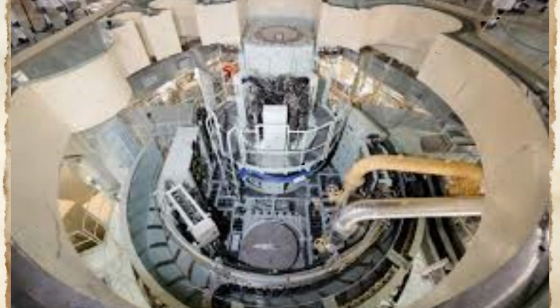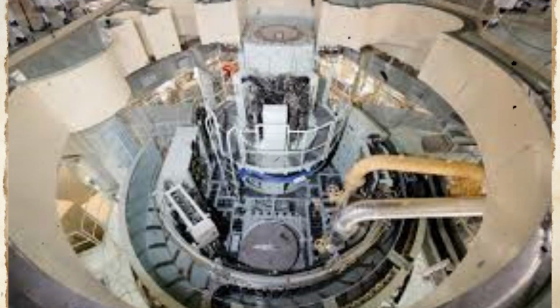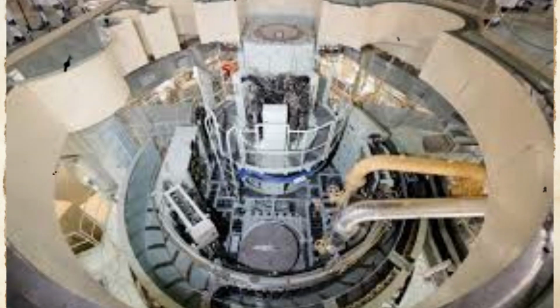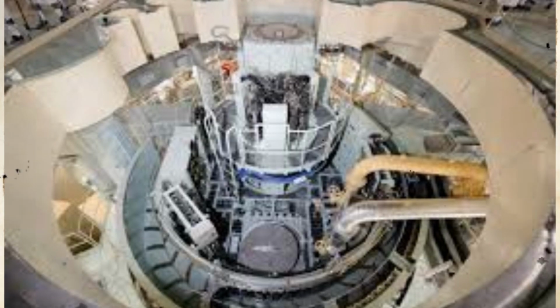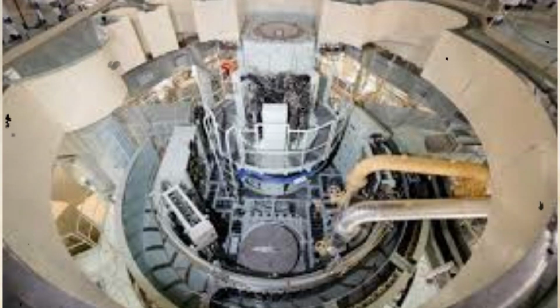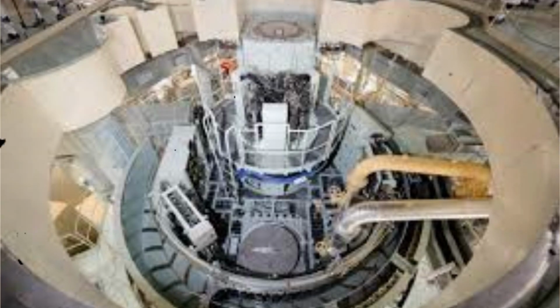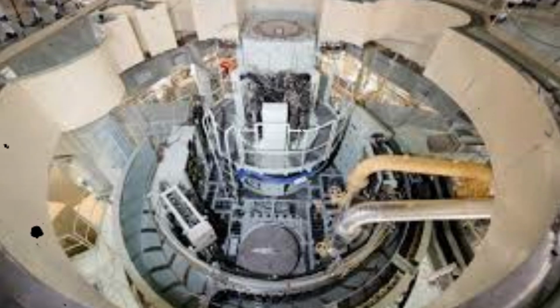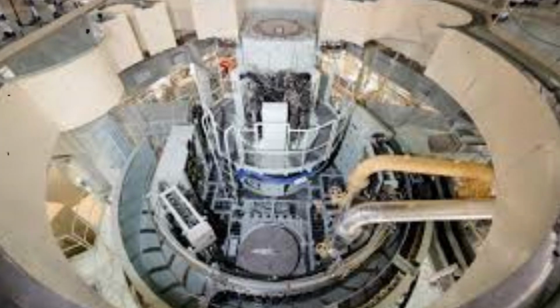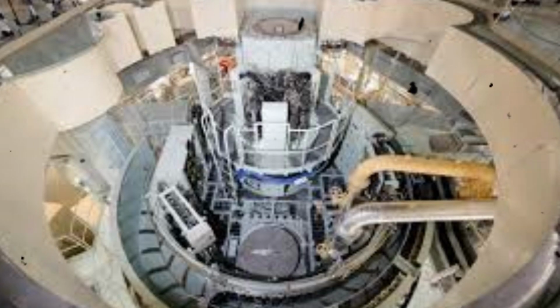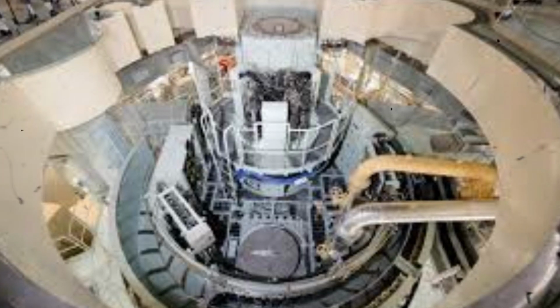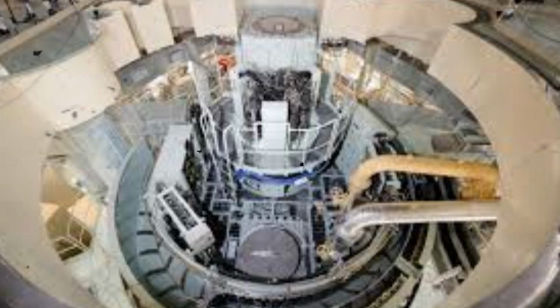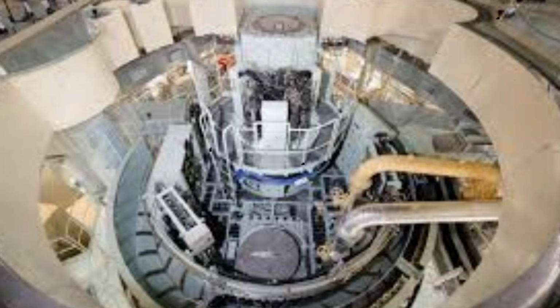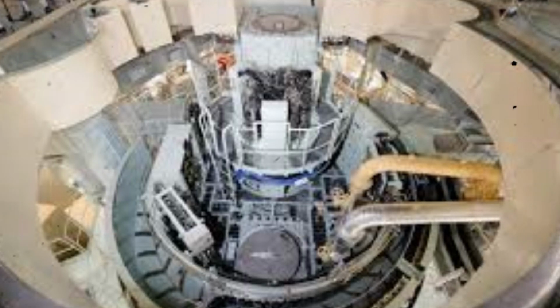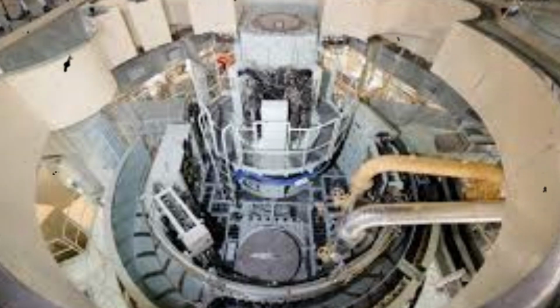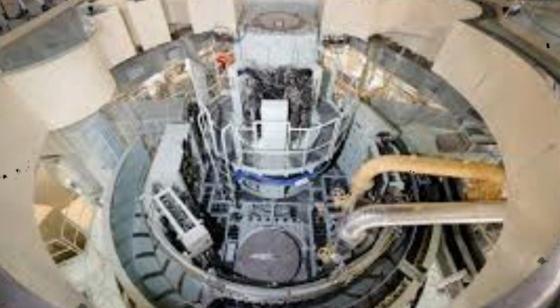The compound distribution indicated that sodium had been ejected with sufficient energy to travel several meters from the leak point before settling and oxidizing. The heaviest accumulations occurred directly beneath the leak source, with lighter distributions extending throughout the room according to airflow patterns and splash trajectories. Chemical analysis of the accumulated compounds confirmed that oxidation reactions had proceeded to completion for sodium that had sufficient contact time with atmospheric components. Compounds closest to the leak point showed higher concentrations of incompletely oxidized sodium, indicating that reaction rates were limited by oxygen availability rather than reaction kinetics in regions with high sodium concentrations.